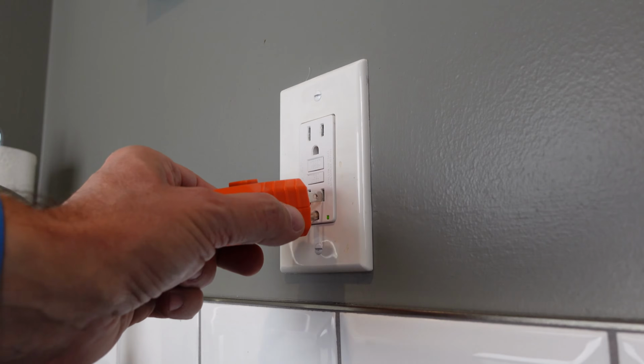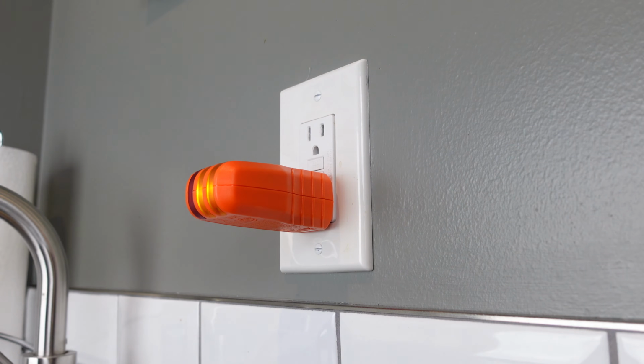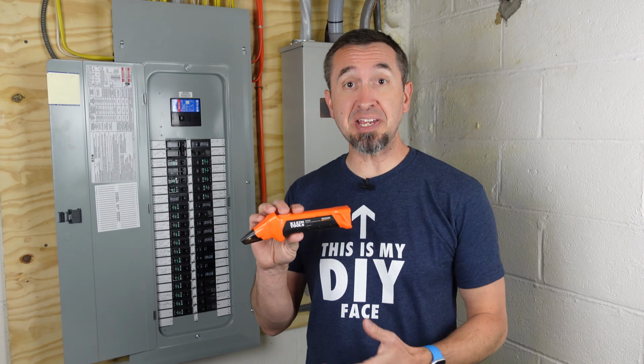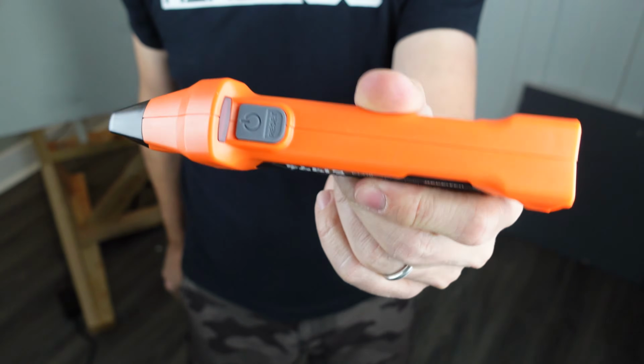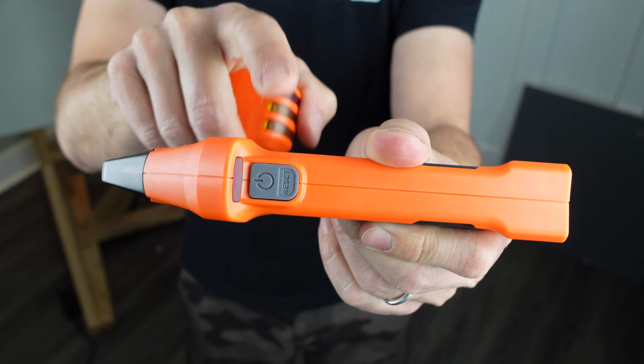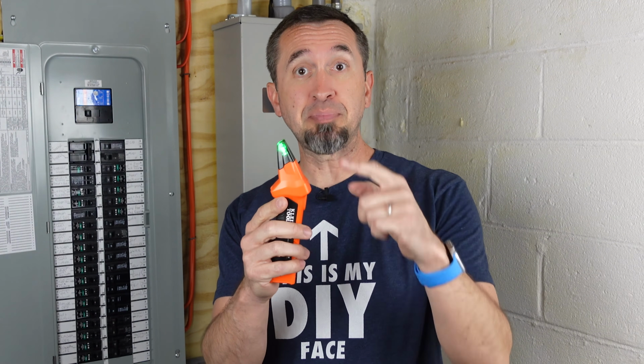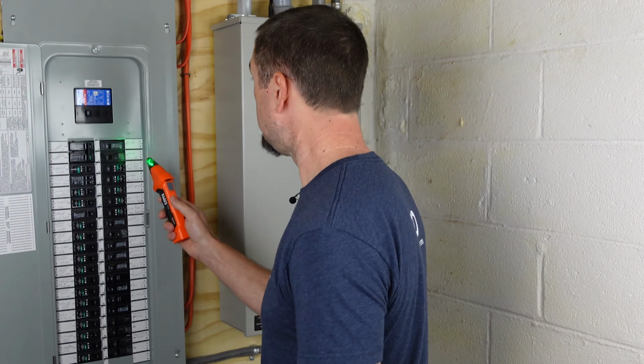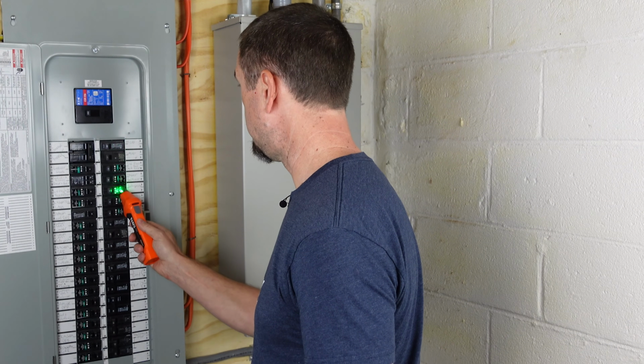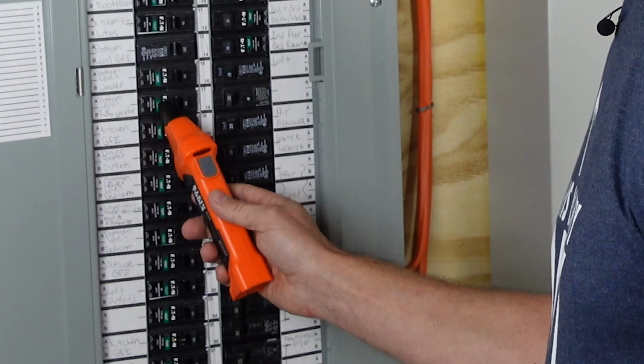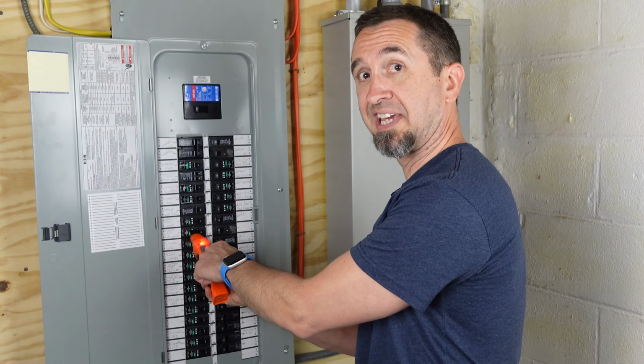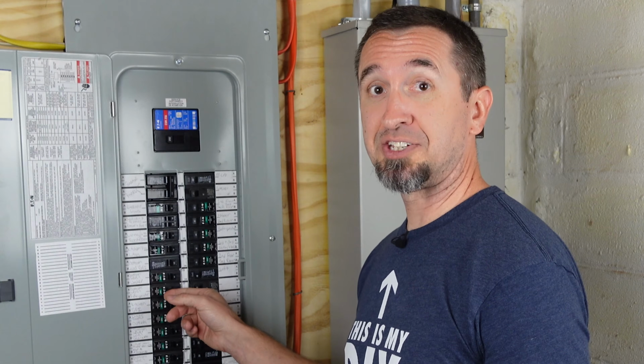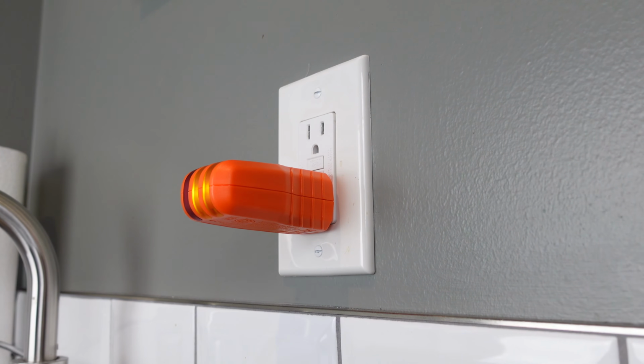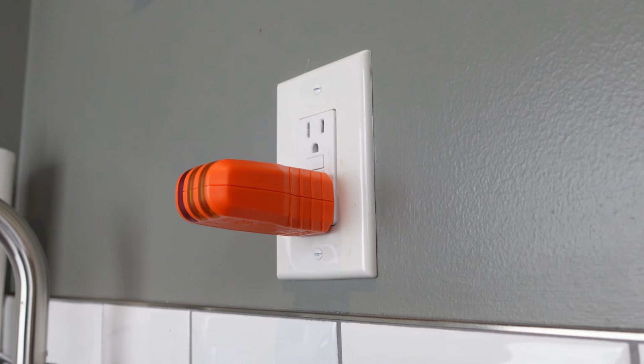So how does this help you figure out which switch to flip in your panel? First, plug the transmitter into the outlet you're trying to kill power to. Then take the receiver to your electrical panel. There's a button on top you press to turn it on - you'll hear beeping and see the green light. Go to your panel and trace down your circuit breakers until you get the red indicator. Flip that switch, and you'll notice the lights on the transmitter have powered off, indicating no power.